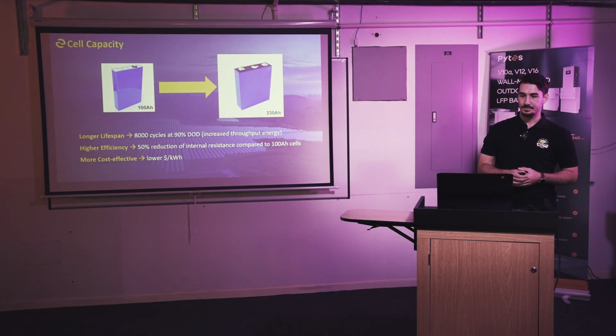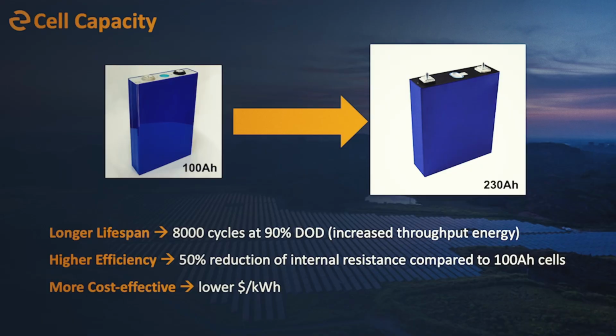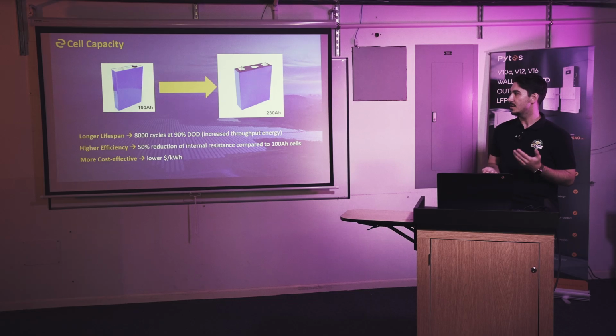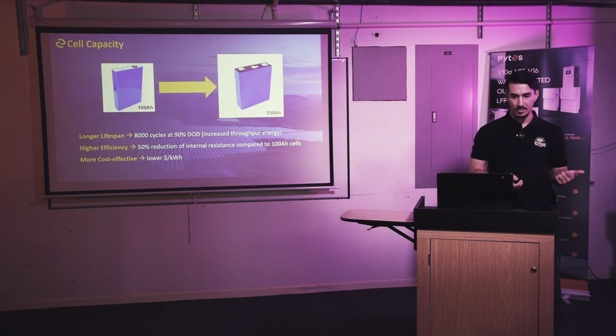What's behind the upgrade here, or one of the core elements, is a larger cell capacity. All of our other low voltage solutions until now have been employing 100 amp hour, 3.2 volt lithium iron phosphate prismatic cells. With V10, we've increased that to a 230 amp hour cell, but we've rated the battery at about 200 amp hours, mostly to extend the life of that battery as much as possible and increase the total energy throughput as high as we can. That said, in addition to that capacity limitation, you're going to get a much longer lifespan with this compared to V5, compared to Pi, compared to e-Box.